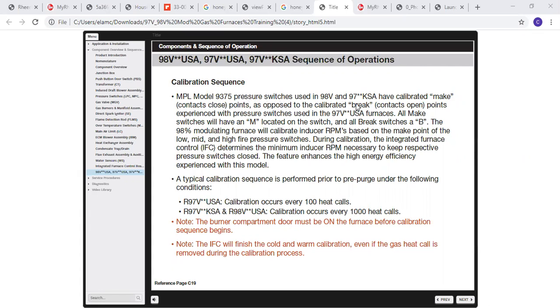The switches used in the 98V and 97 KSA have calibrated make close contact points, as opposed to the calibrated break contact points with the 97 USA. All make switches will have an M located on the switch, and the break switches will have a B on the switch. The whole process is to calibrate the inducer RPMs. It's a learned process to calibrate the low pressure switch, the mid, and the high fire.